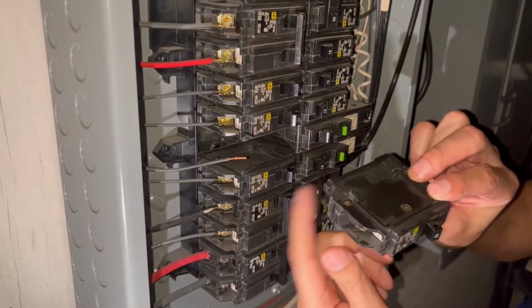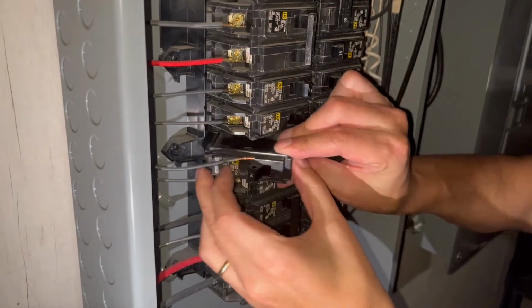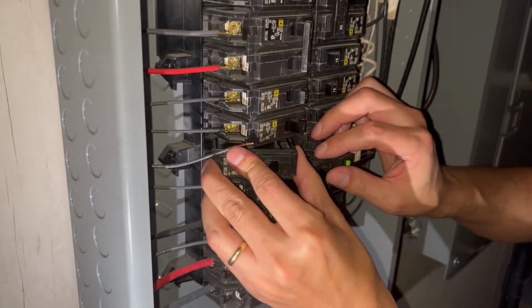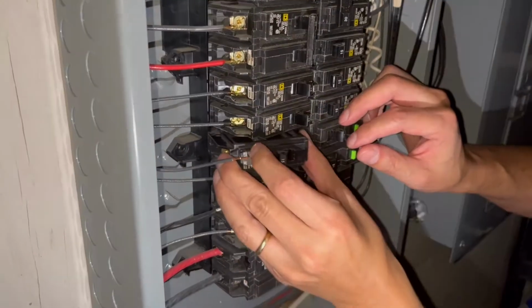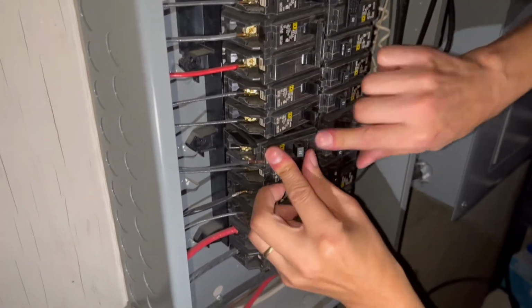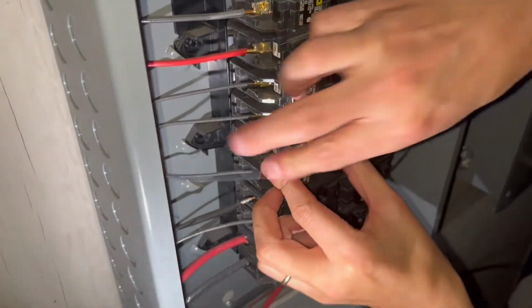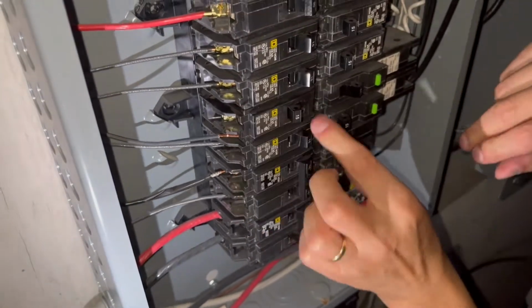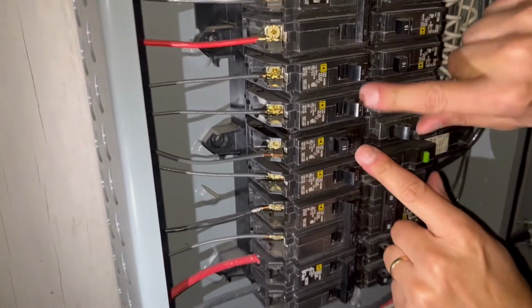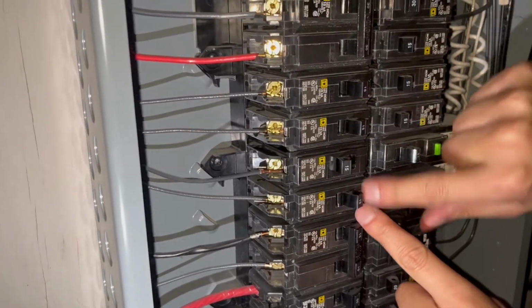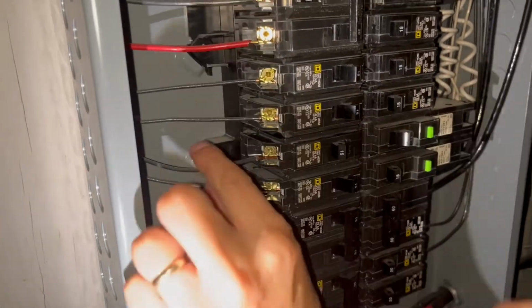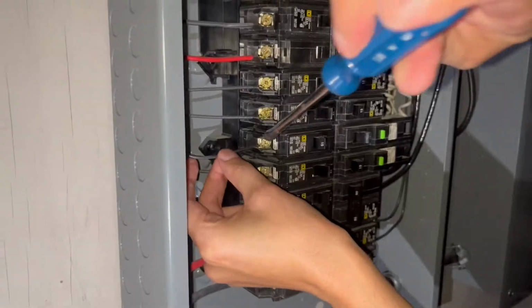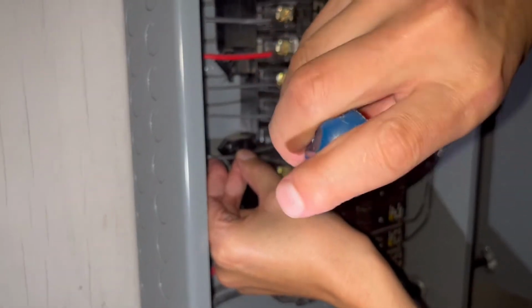You start by putting the back corner in, and it's going to almost feel like a hinge. It's actually going to lock right in place. And then this part here will snap right in. There you go. So if you have it correctly, it's snapped in tight. It matches the existing circuit breakers. If they're all lined up, you've done it correctly. Now we have to reattach that wire. The wire goes right behind that plate, and then you simply tighten it on down.